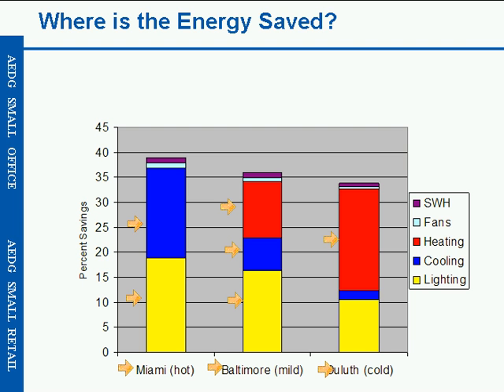One of the advantages of the guide over some previous work is that it really looks at the integration of systems. These savings were based on whole building savings, so that when you start reducing your lighting loads, that also impacts your HVAC loads. Those savings were accounted for in this guide, and that interaction was taking place, which is one of the reasons that it's important on the design side to think about the envelope and the lighting first, and then design the HVAC to match whatever remaining loads you have.